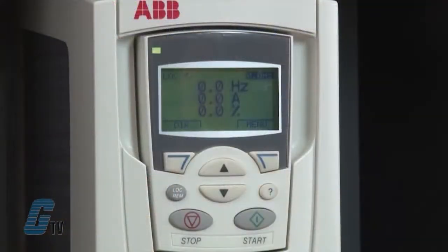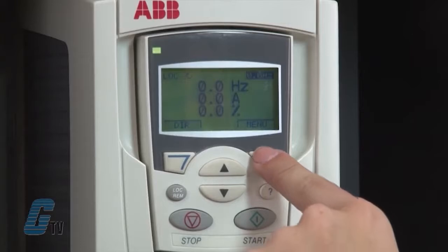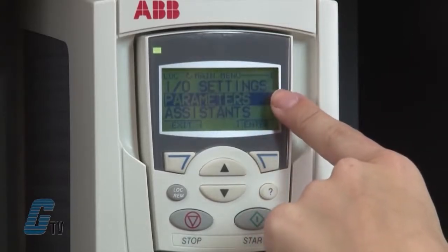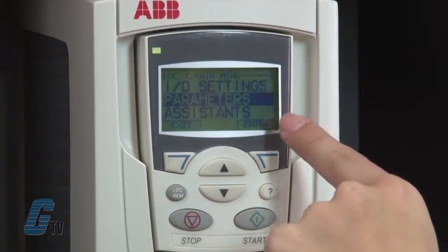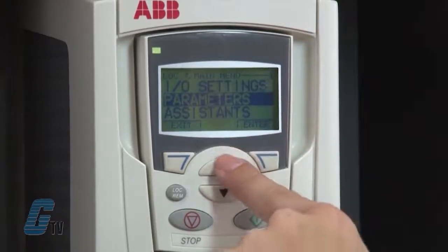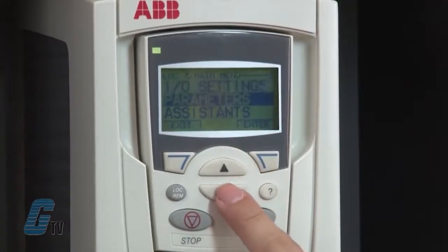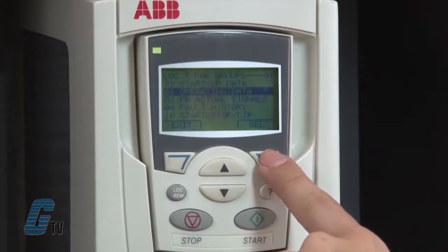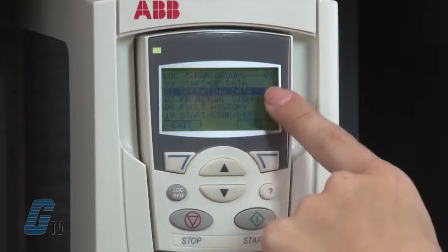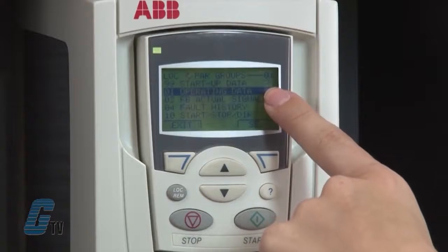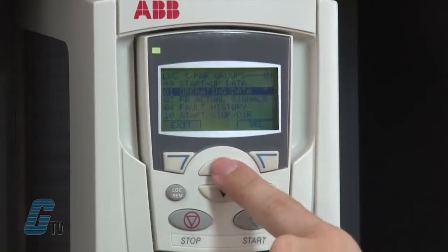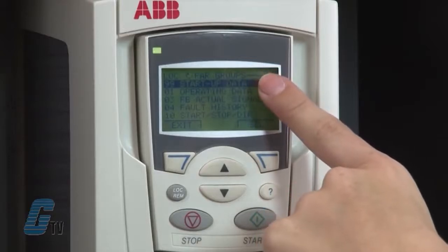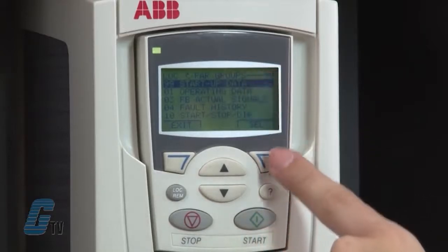First, I will push the menu button, which is currently the right soft key. The word 'Parameters' should be highlighted. If not, I will use the up and down arrows to highlight it. Now I will push the soft key for enter. The display will now show the parameter groups by number and description. Group 01 should be highlighted. I will push the up arrow once and group 99 startup data should be highlighted, then I will push the select button.